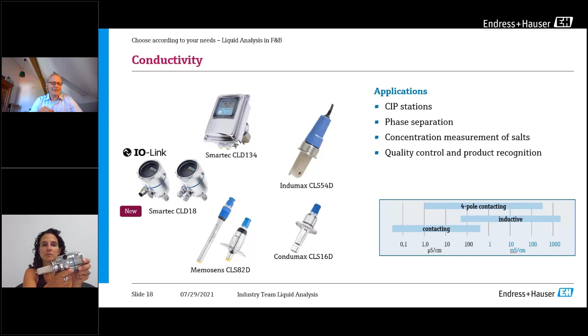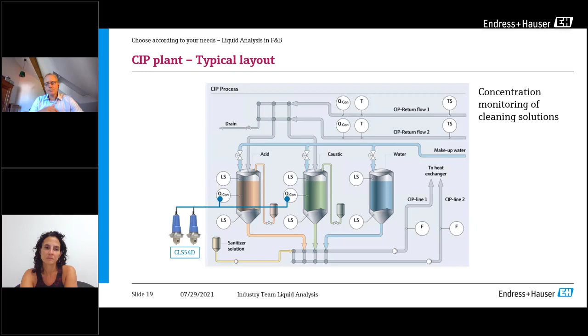Good. Now we come to a couple of examples, and the first one is a CIP plant. You see the typical layout with the different vessels for the acid, caustic, and the water. Typically the first sensors are installed in the vessels to adjust the concentration of the cleaning solutions. The second sensors are in the return line. The solutions go into the process, the cleaning is done, and then they are returned. Here the aim of the sensor is phase separation: what is the concentration of the cleaning solution, can we reuse it, or do we have to send it to drain?